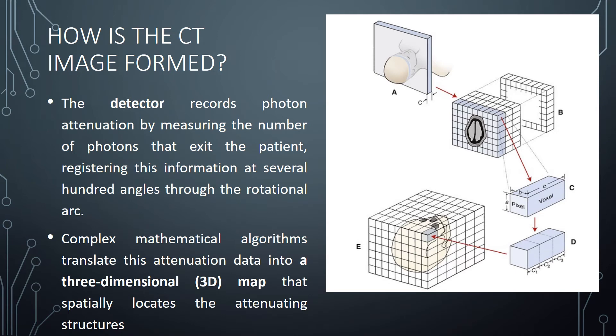So how is the CT image formed? The detectors record photon attenuation by measuring the number of photons that exit the patient and registering this information at several hundred angles throughout the rotational arc. The X-ray source and the detector are both rotating around the patient, so multiple exposures are made from different angles and captured by the detector. These are then combined using a complex mathematical algorithm, translating the data into a three-dimensional map that constitutes the image we see.